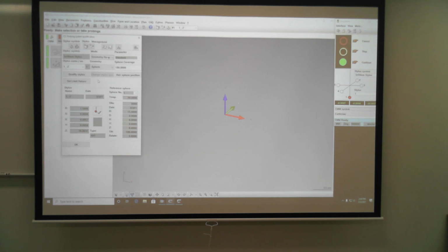It's not going to prompt you to touch your own point. So that's why before I told you, normally I position the probe before I even start this. And the reason is, depending on what you're doing, it may move diagonally over to get to the sphere, and there may be something in the way. So if you just always position the sphere roughly in the correct location before you start, now it doesn't matter what you do, it's going to be safe.